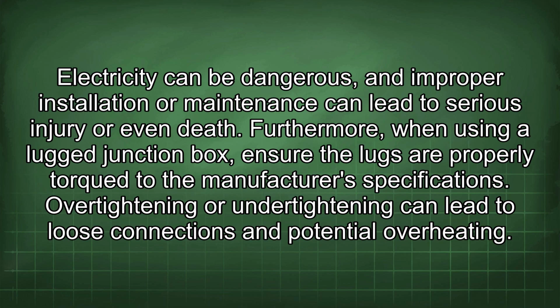Furthermore, when using a lug junction box, ensure the lugs are properly torqued to the manufacturer's specifications. Over-tightening or under-tightening can lead to loose connections and potential overheating.